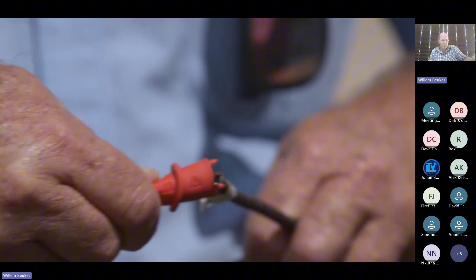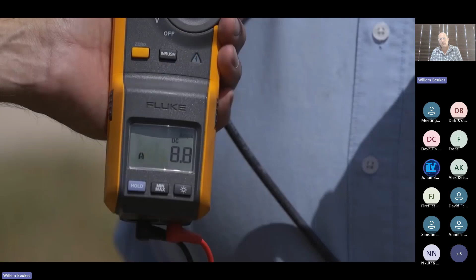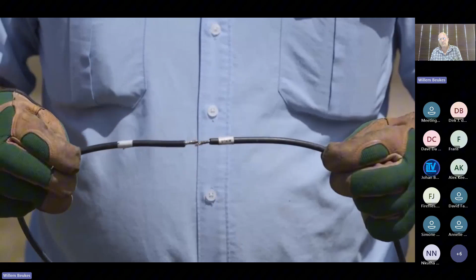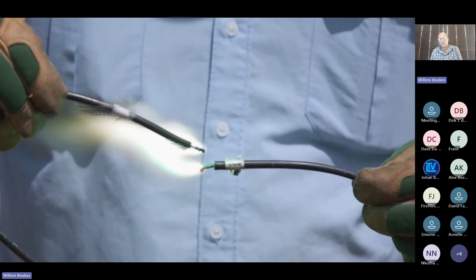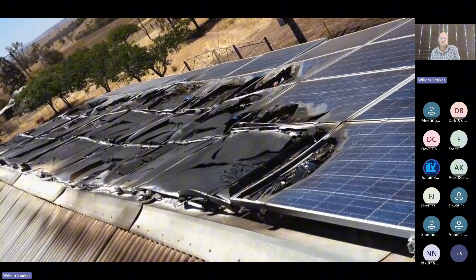Next, we connect a voltage meter and an amperage meter to the array to measure the electrical output. As you can see, even though every panel in the solar system is damaged, the system is still producing over 650 volts open circuit and nearly 9 amps short circuit current. This is a lethal amount of DC electricity, as you can see by the electrical arc we're drawing between the positive and negative wiring. This demonstrates that even when every panel in the system is damaged, solar systems continue to produce potentially lethal amounts of DC electricity. Even when seriously damaged by fire, solar panels continue to be a serious safety risk.